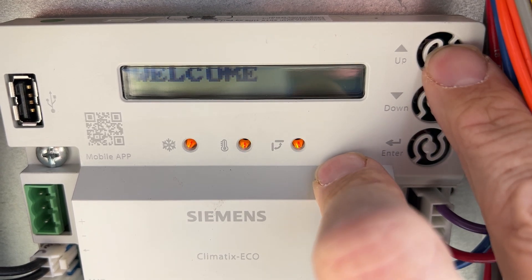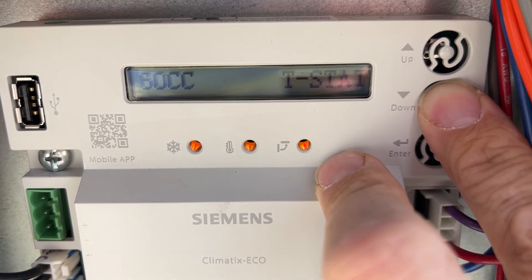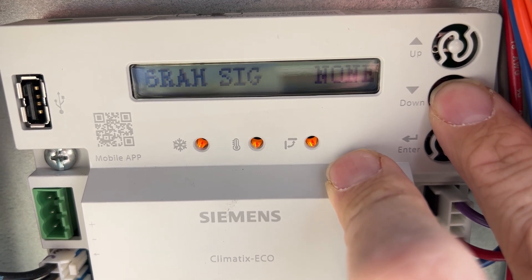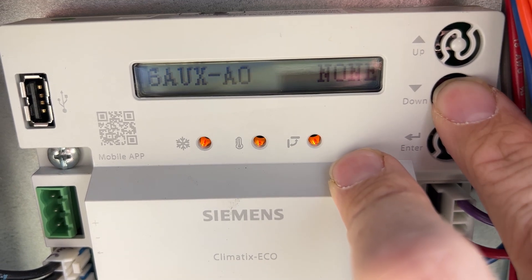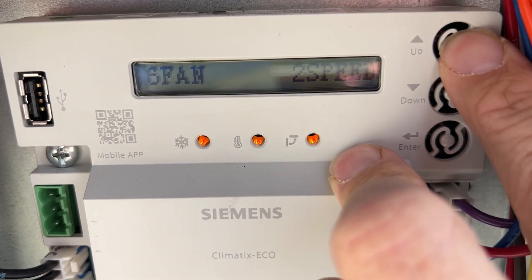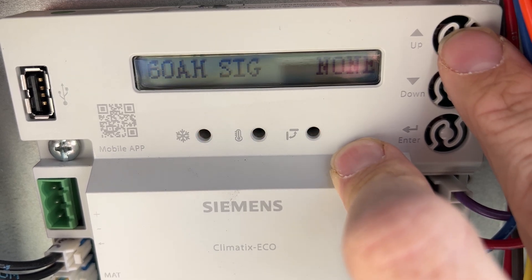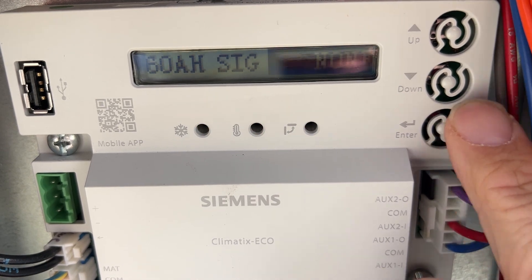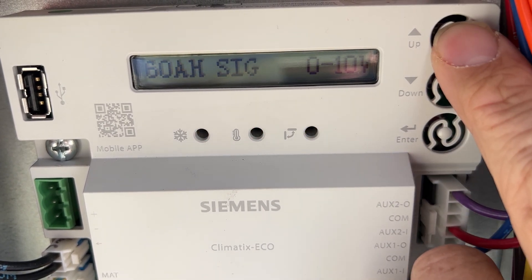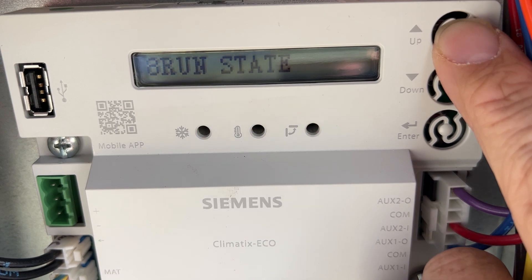In here we want to go to item six: OAH SIG. Item six, OAH SIG, currently has a value of 'none.' Change that to two, which is the 0-to-10 signal. Press enter, then you'll need to go to the eight run state to save the change. It will reset the control.